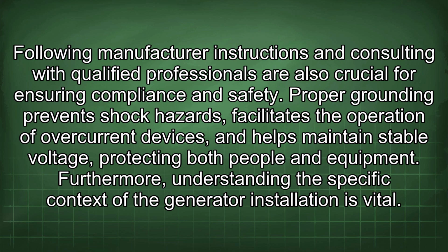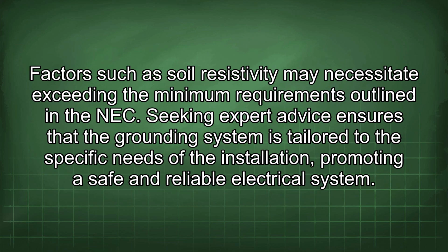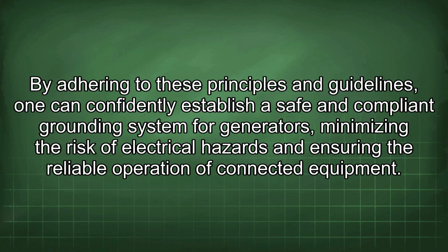equipment. Furthermore, understanding the specific context of the generator installation is vital. Factors such as soil resistivity may necessitate exceeding the minimum requirements outlined in the NEC. Seeking expert advice ensures that the grounding system is tailored to the specific needs of the installation, promoting a safe and reliable electrical system. By adhering to these principles and guidelines, one can confidently establish a safe and compliant grounding system for generators, minimizing the risk of electrical hazards and ensuring the reliable operation of connected equipment.